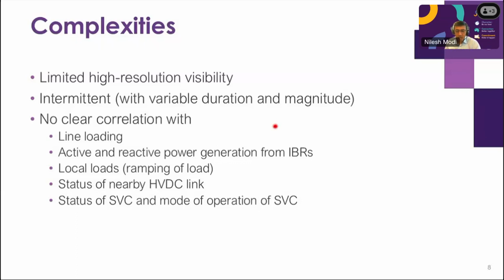There was the HVDC link, so some of the literature suggested that the HVDC link could have an impact on this or could be a cause of the oscillation. But when this HVDC link was out of service, we could still see oscillation. So the status of the nearby HVDC link was also ruled out. We looked at the status of the SVCs and the mode of operation of the SVC. We put one of the SVCs in a manual, Q control mode, just to isolate whether it is a cause or not. But we couldn't find any correlation with the SVC as well.